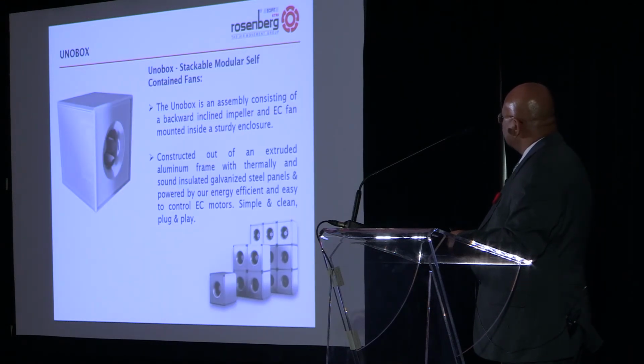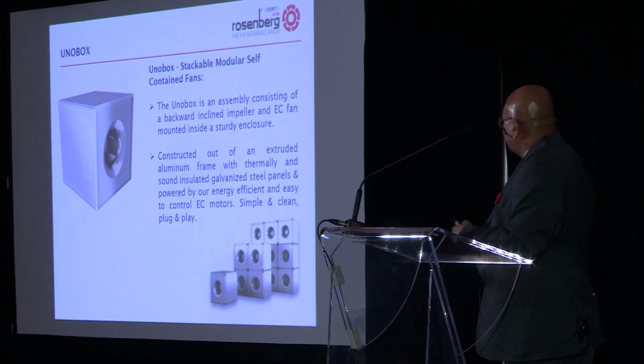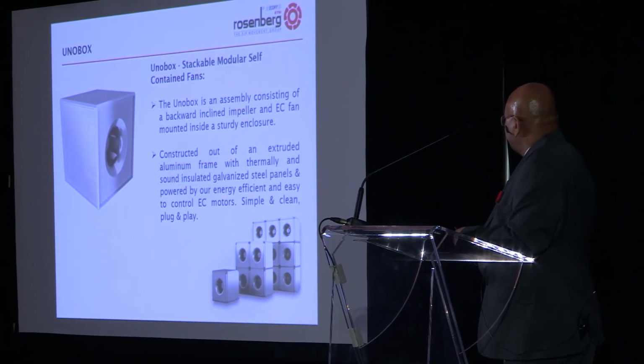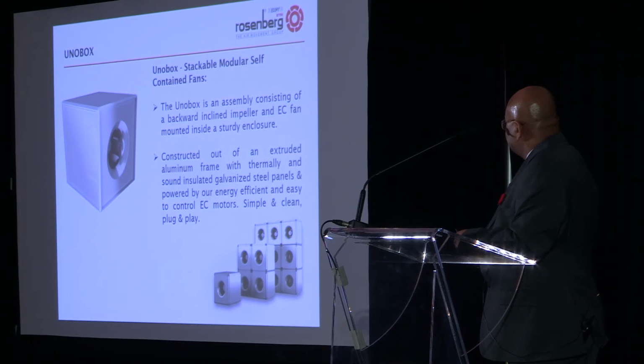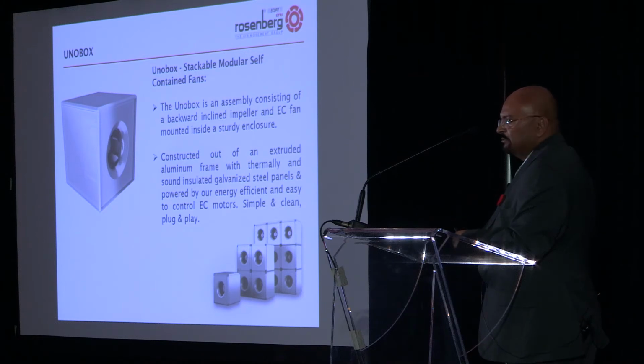Now we are in the Unobox section, which is the third configuration I was talking about in my previous slides. A Unobox is an assembly consisting of a backward inclined impeller and an EC fan, again with the ECM technology, inside the enclosure. The box is made of extruded aluminum frame, with galvanized steel panels, powered with our energy efficient and easy to control EC motors. It's very simple, plug and play. You can use these Unoboxes for any installation. You can just stack the boxes together to the opening and it's plug and play.